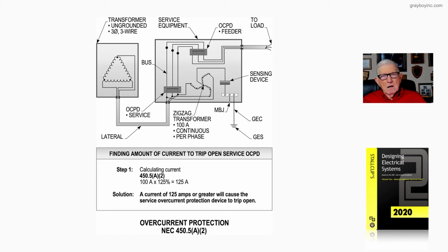But notice our zigzag transformer is 100 amp and it's rated for continuous per phase. So in the boxed in information, we're finding the amount of current that would be needed to trip open the service overcurrent protection device that you see in the left-hand bottom side of the enclosure of the service equipment. So after we do our math in step 1 in accordance with 450.5(A)(2), 125% of 100 would be 125. So the overcurrent device would be sized at 125 amps or greater.